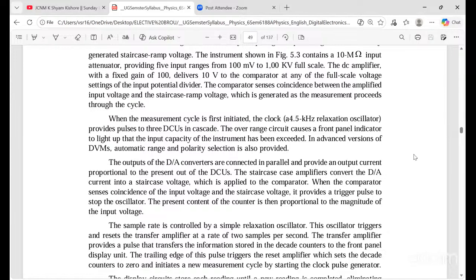And the DC amplifier, which fixes the gain at 100, delivers 10 volts to the comparator at any of the full scale voltage settings of the input potential divider. The comparator senses coincidence between the amplified input voltage and the staircase ramp voltage, generated as the measurement proceeds through the cycle.